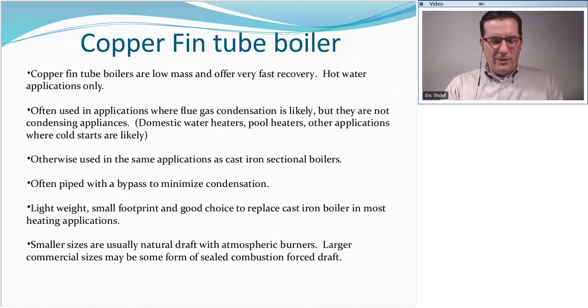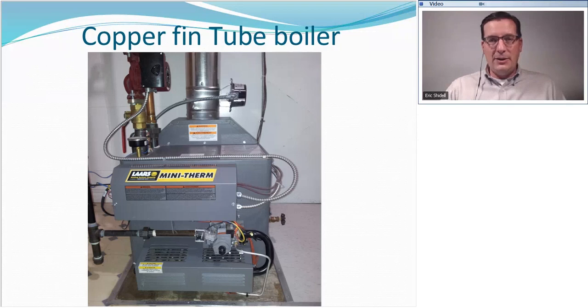Okie dokie, welcome back from break, everybody. We were in the middle of talking about copper fin tube boilers. In keeping with what we discussed earlier about identifying what kind of boiler you have and what direction the water is moving, the copper fin tube boiler is a little more difficult to identify which direction the water is moving. Now, when they come from the factory, there's a label. One side says supply, one side says return.